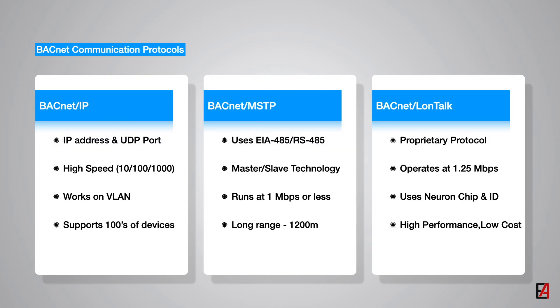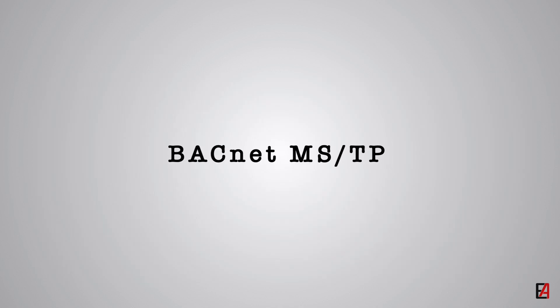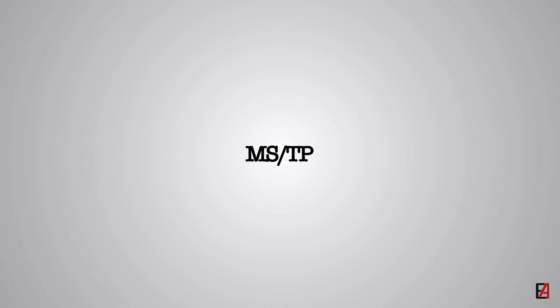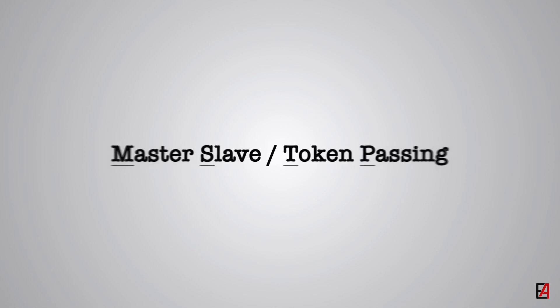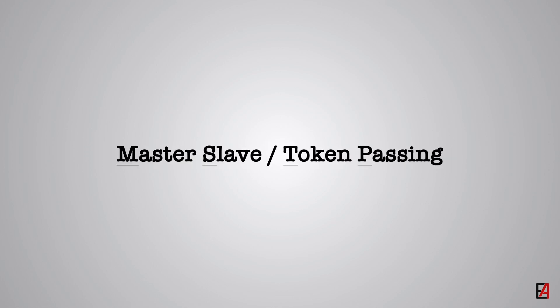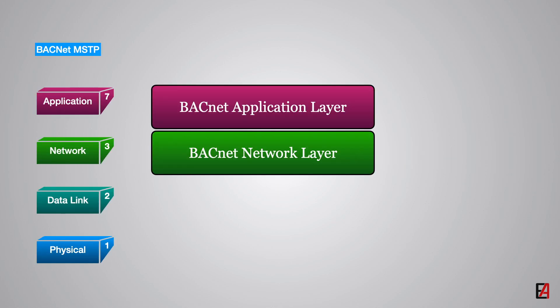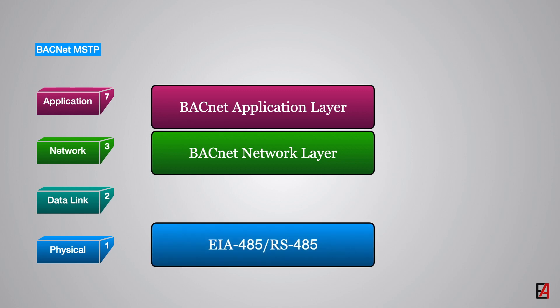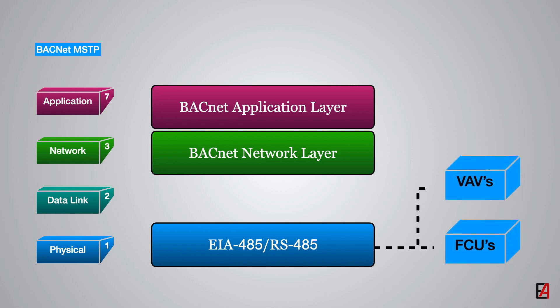In today's video, we will learn about one of the most widely used BACnet LAN technologies, BACnet MSTP protocol. The MSTP stands for Master Slave Token Passing which uses EIA-485 standard at the physical layer. It is one of the most used physical layer technologies in building control systems, particularly for application-specific controllers such as FCU and VAV controllers.